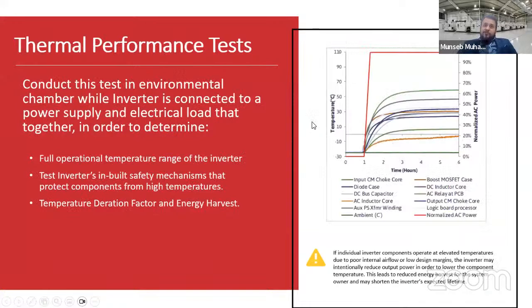And then if you do the environmental test when the inverter is connected to a power supply and the load, you can do the testing for the full operational temperature range of the inverter. You can test the inverter's inbuilt safety mechanisms that protect the inverters from the high temperatures, and you check the Temperature Deration Factor and actual energy harvest from that particular inverter under high temperatures.